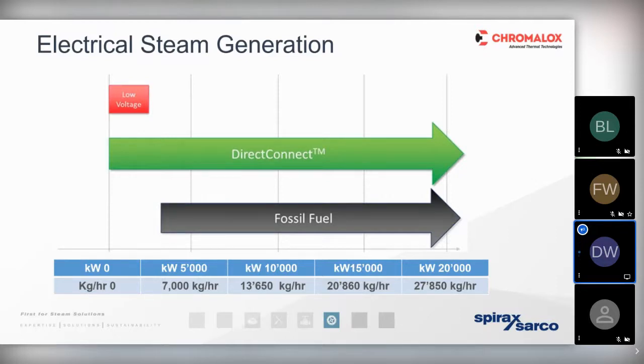And that's because of very, very similar water treatment levels. Do you remember we refer to that as the total dissolved solid content or the TDS levels? They're going to be very, very similar. So once again, it's likely to be a possibility that we can simply retrofit the traditional boiler utilized in fossil fuels. We can retrofit the burner that furnishes the boiler with either hydrogen or an electrical heater element in order to generate steam sustainably from an alternative fuel source.